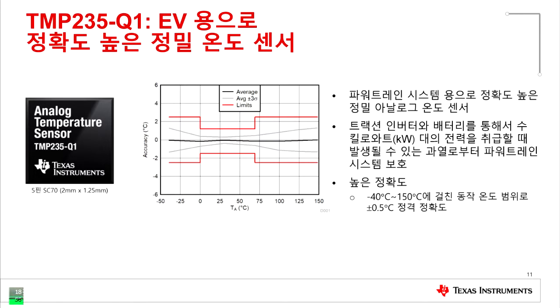So whether this is IGBT, silicon carbide, or standard FET-based, there are power losses, and you want to monitor them. Traditionally, this was done with NTCs, which have some shortcomings, especially at high temperatures. The tolerances of these were so high that you cannot provide appropriate control of your system at high temperatures.